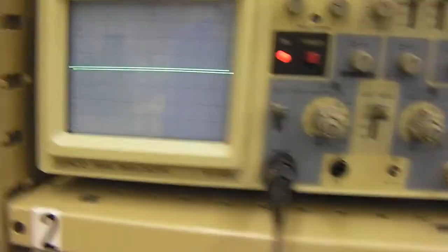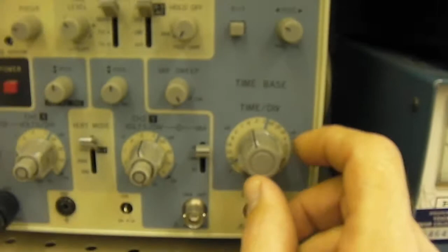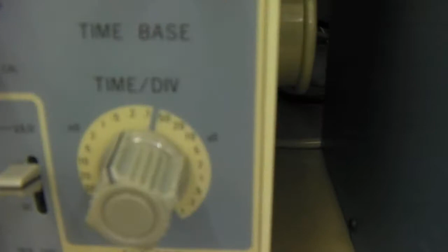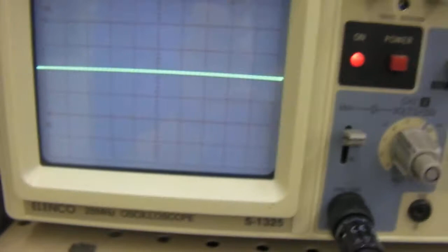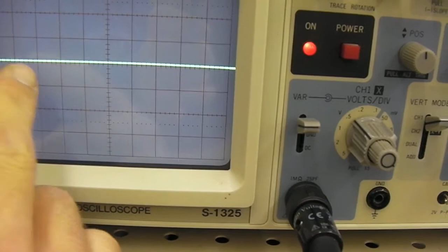Okay. And then it says to set the time per division control for about 1 millisecond. So what's that? Well, that's over here. What that control does is time per division controls how long it takes the dot to move across the screen. And specifically what it does is it tells how long it takes the dot to move across one of these divisions, or little squares on the screen there. Each one of these little squares represents a certain amount of time. So you can see if I turn it really slow, you see it takes a certain amount of time.